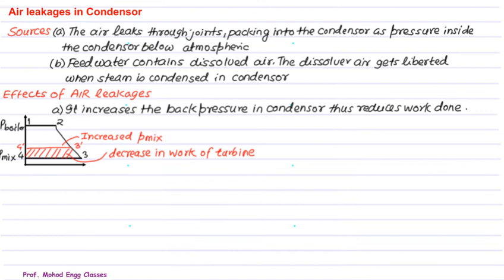If the back pressure increases from 4 to 4 prime, thereby you have reduced work 1, 2, 3, 4 prime, and therefore there is a decrease in the work of turbine by the quantity 4, 3, 3 prime, 4 prime. This is the ill effect of air leakage in the condenser.